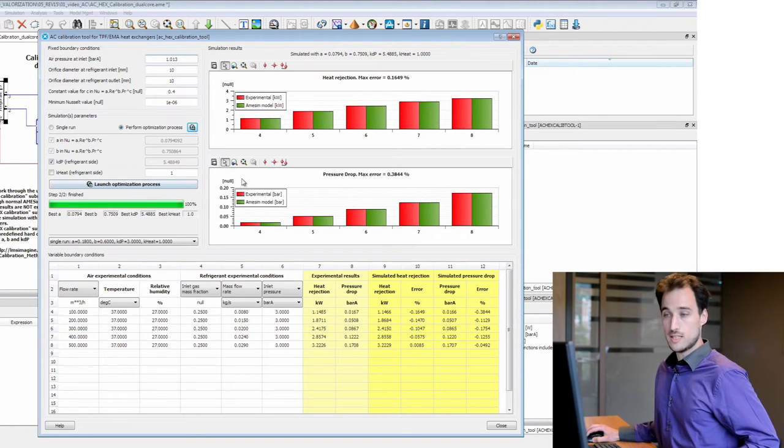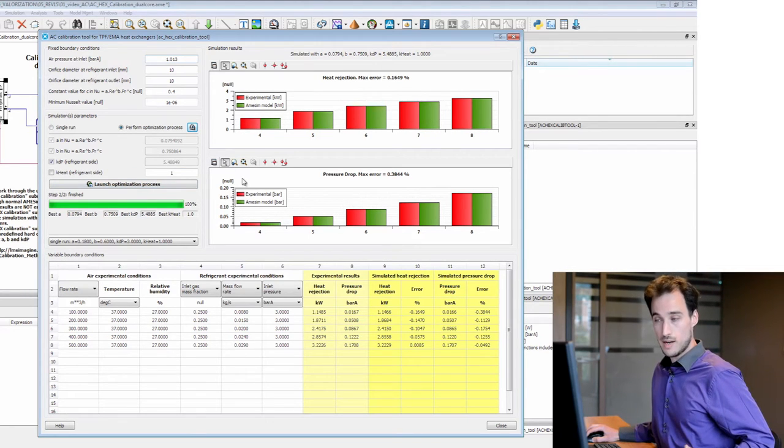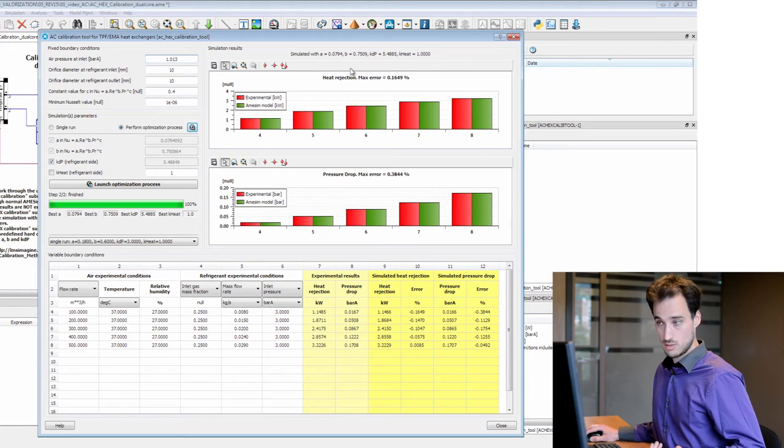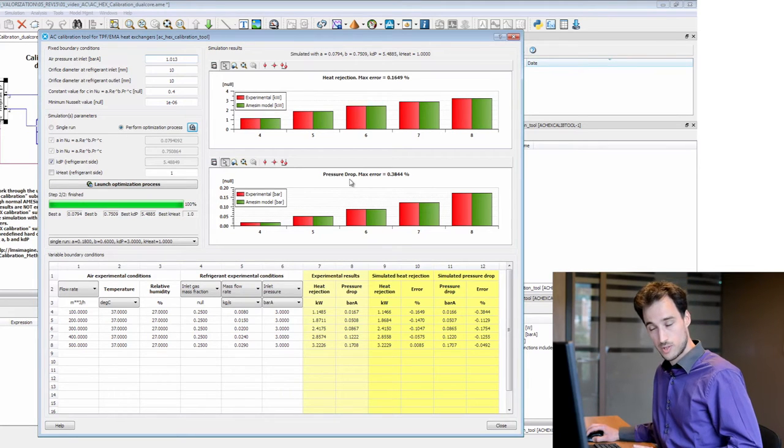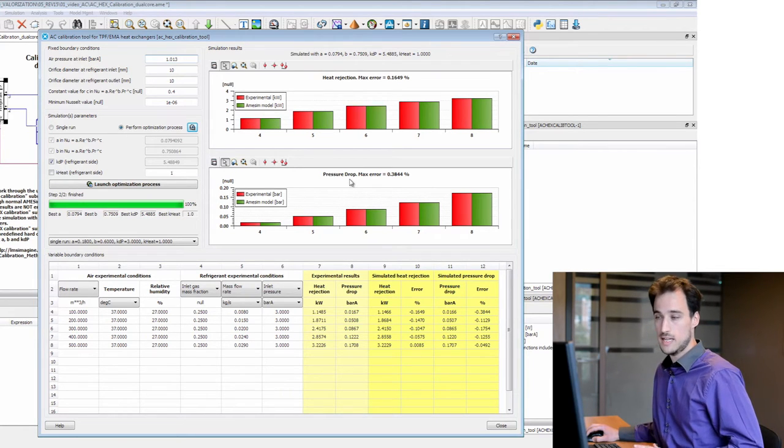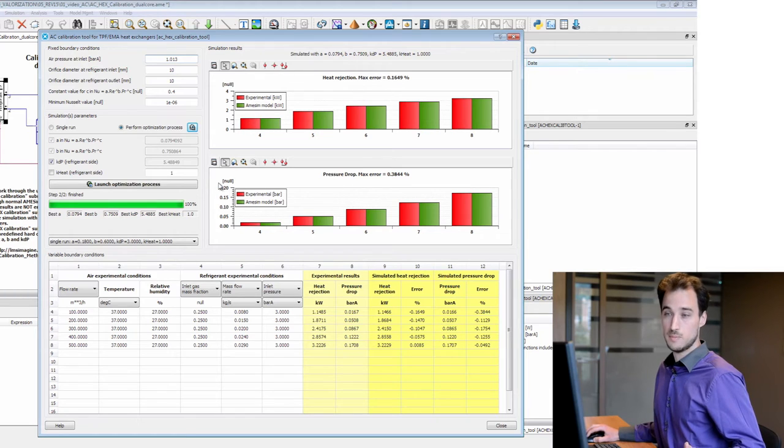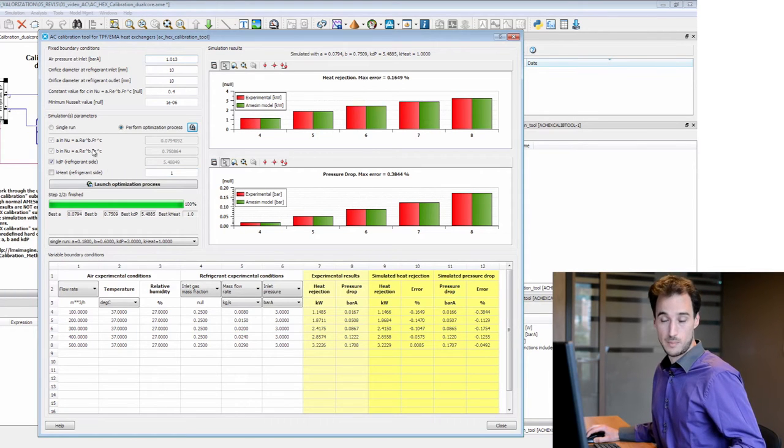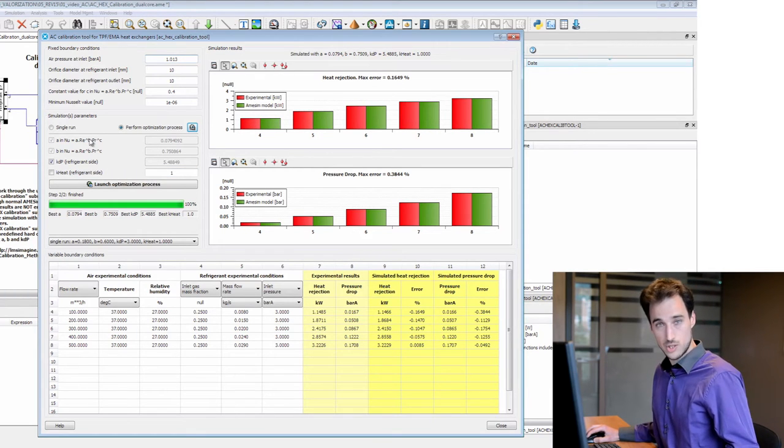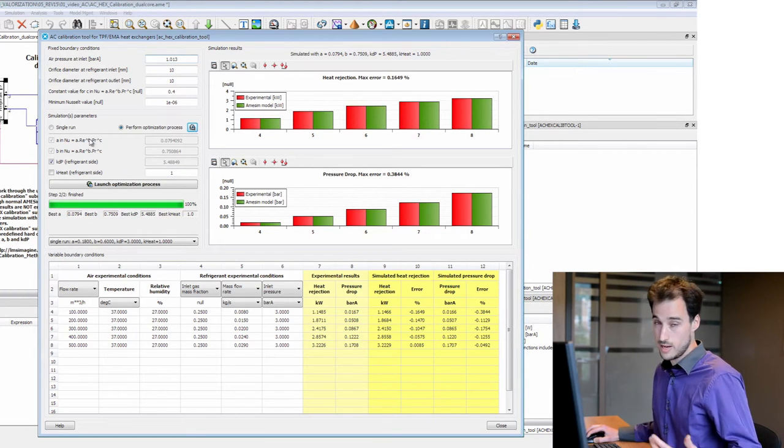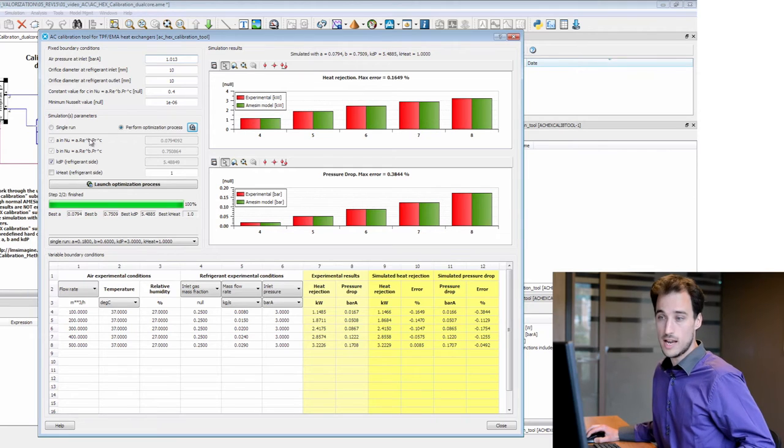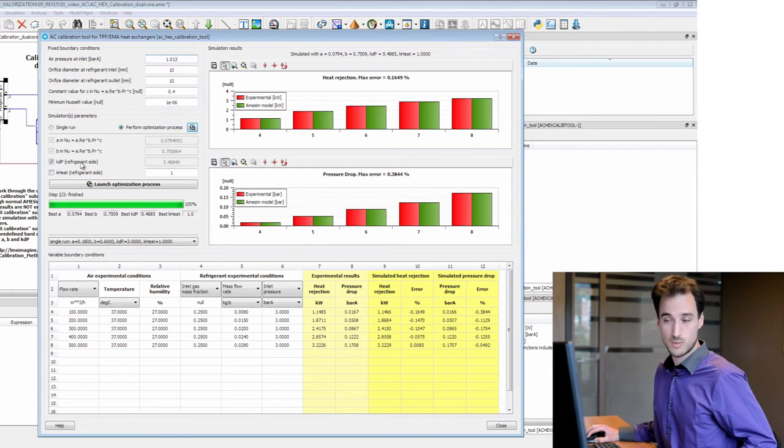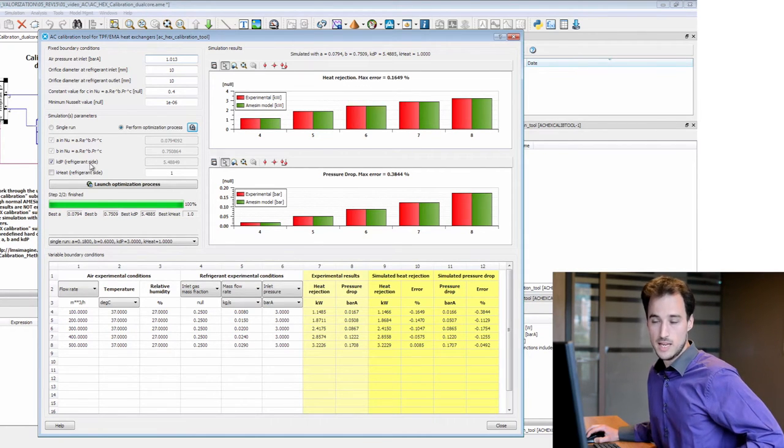The goal is to minimize two things: heat rejection and pressure drop at the refrigerant side. This is done by modifying some parameters which are the initial correlation for the air flows and a pressure drop gain for the refrigerant side.